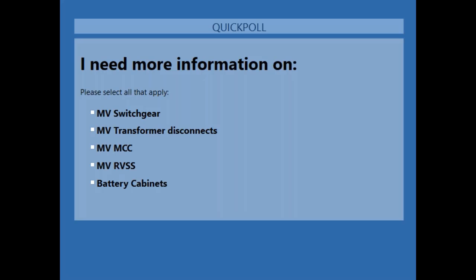Yeah, I would add, in answer to the question, I see the question here asked, what happens if you're a 6'2", 250-pound guy, is that going to be a problem? And my answer to that would be, when you're looking at compact switchgear, that it depends. If you're looking at metal enclosed gear that's fusible, the front to back configuration you mentioned, Michael, that could be a greater challenge for a large individual. But in general, compact gear, as a general rule, is easier to maintain no matter what your size.